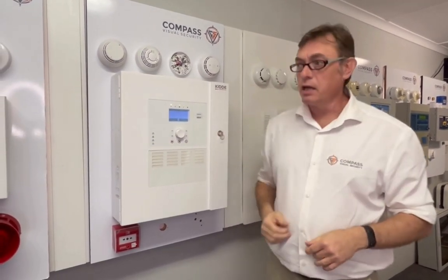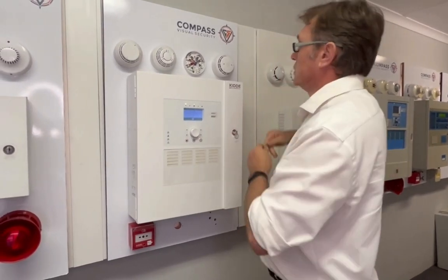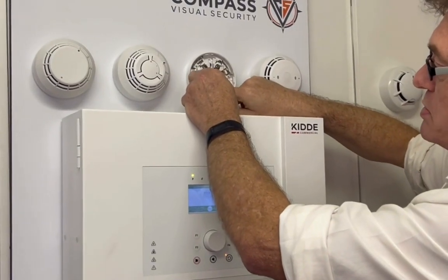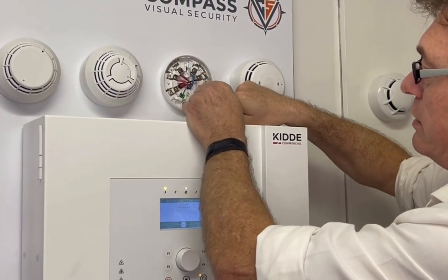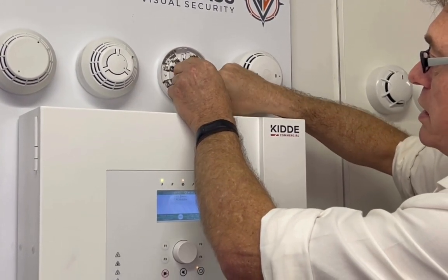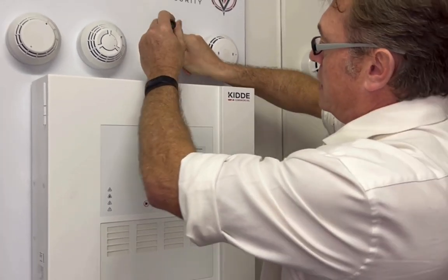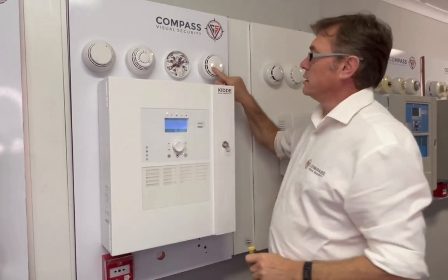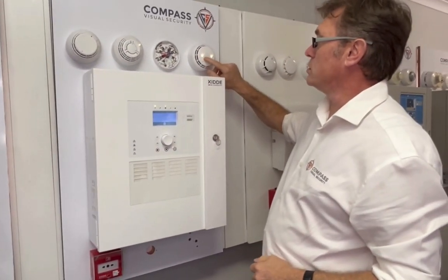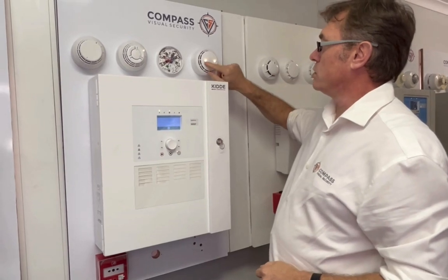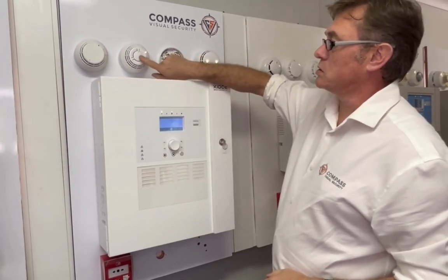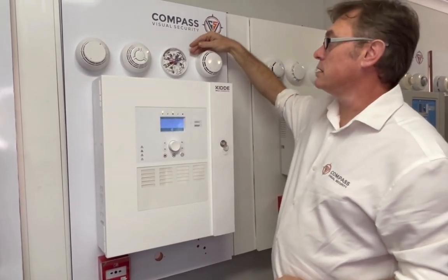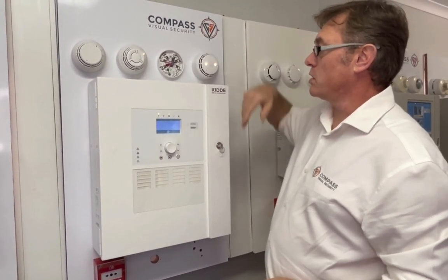So if we want to test it, I can create a short circuit on the loop now. Where I've got my positive, it's a plus A and a plus B, so it comes in on A and goes out on B. I've got a negative A and a negative B. So let's say I take this one and, by mistake, connect it to the negative. You'll see straight away this detector has now gone into isolation mode. So it's solid yellow, and that one is also gone solid yellow. So this section of the loop is now being isolated, and the rest of the loop will still be operational.